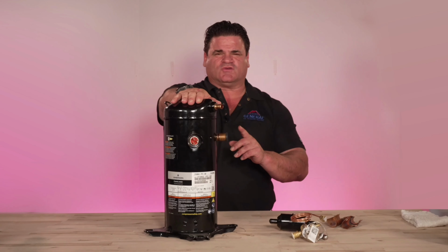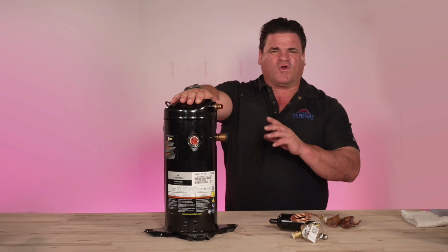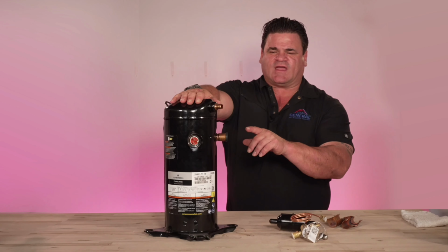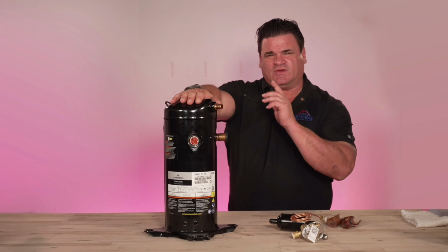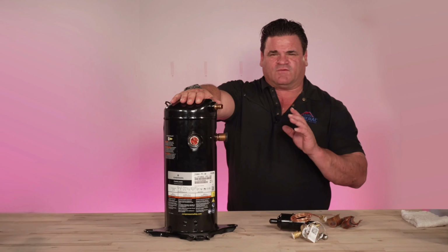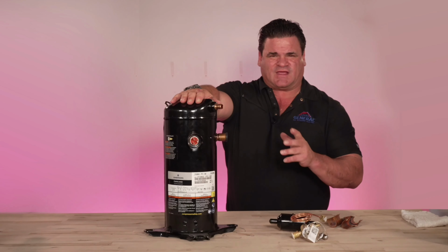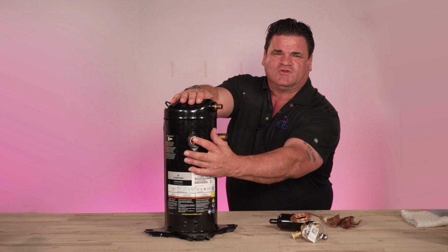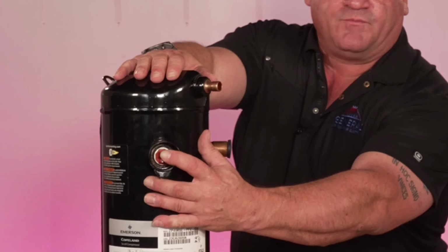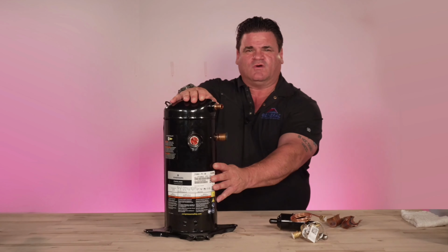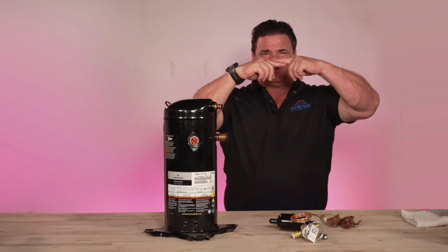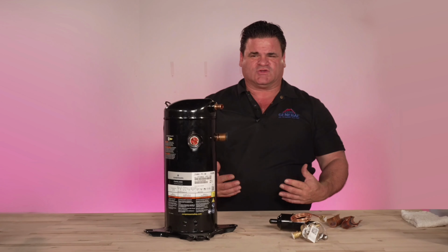Important to know, if you have a commercial structure and you have three-phase power, or in the rare instances you come across three-phase on a residential, how you check the windings on a system that uses three-phase power is totally different. So very important that you understand that. The technician obviously understands. But you're going to measure these windings. I won't go into what windings you measure and whatnot. But basically, you measure all three of them, and it'll tell you if this is out on internal overload. If this is out on internal overload, it needs to cool. And as it cools, those dissimilar metals will connect and power will be restored to the compressor.